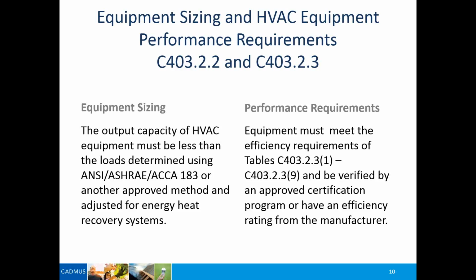And Howard mentioned the fact that we're now requiring that the building envelope be more efficient: better windows, actually continuous air barriers to reduce infiltration loads. So we have reduced solar heat gain coefficient requirements in the windows. We have cool roof requirements on the roofs for flat roofs. All of these will reduce our cooling loads pretty significantly, and they have to be reflected in the load calculations.